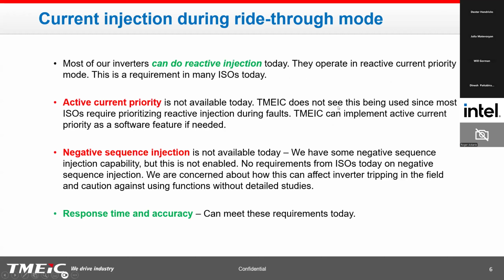So in terms of reactive current injection during ride-through, most of our inverters can do reactive injection today. In fact, this is required by almost every ISO that we know of today, requiring reactive injection during grid events or fault events essentially. The standard specifies the default injection mode to be reactive power priority. So our inverters by default operate in reactive current priority during these fault ride-through events. So that portion of the standard we would be able to meet. But the standard also specifies that you would need the ability to choose between active current priority and reactive current priority. We don't have that feature available today.